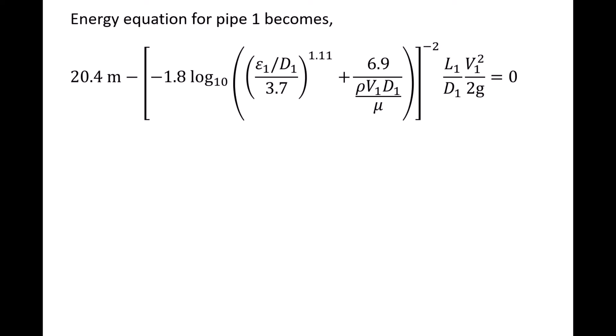We substitute the Darcy-Weisbach and Haaland equations into the energy equation and examine pipe 1. Note that the subscript i has been replaced by the number 1. The diameter, absolute roughness, and length of pipe 1 were already given. At 15 degrees Celsius, the density of water is 999 kilograms per cubic meter, and the absolute viscosity is 1.14 times 10 to the minus 3 newton seconds per meter squared. And the gravitational acceleration is 9.81 meters per second squared. This means the only unknown quantity in the equation is the speed v1. Unfortunately, it's too difficult to solve this equation for v1 through algebraic manipulation. So we have three options.